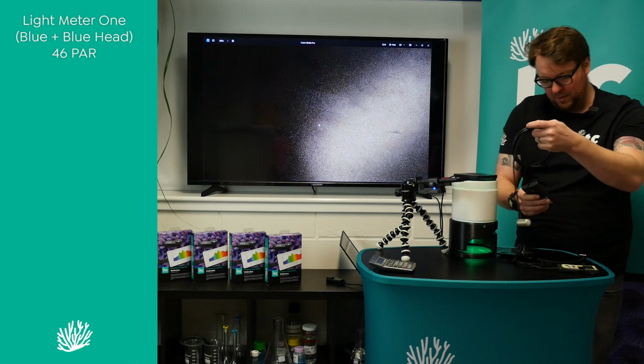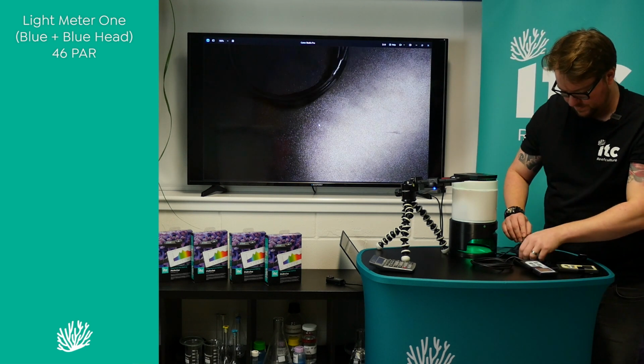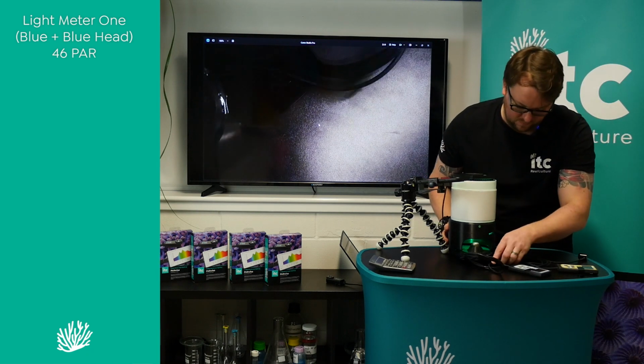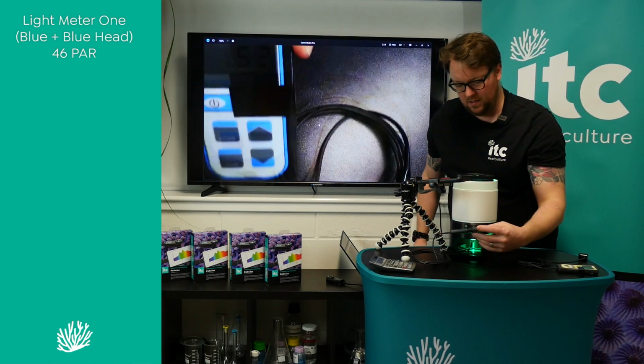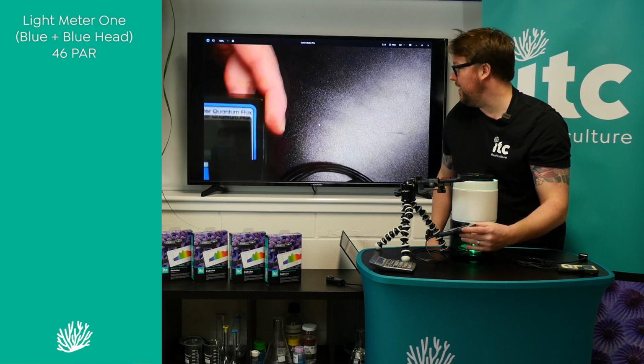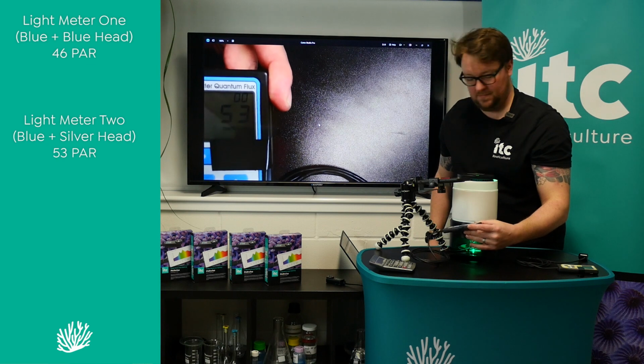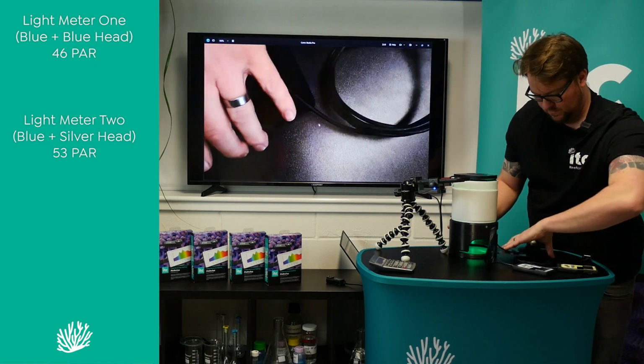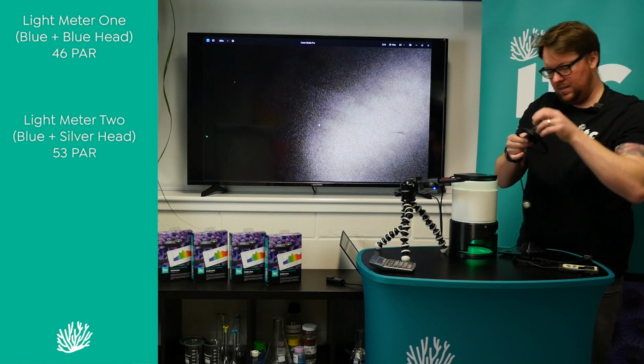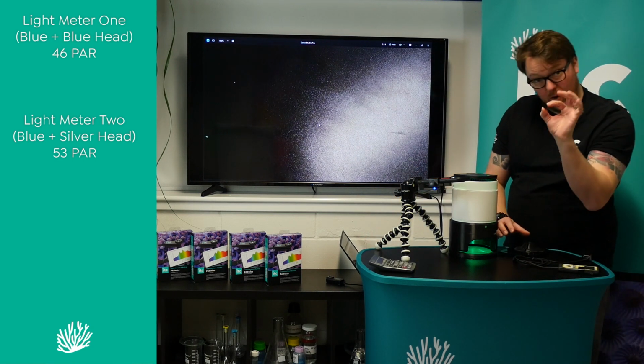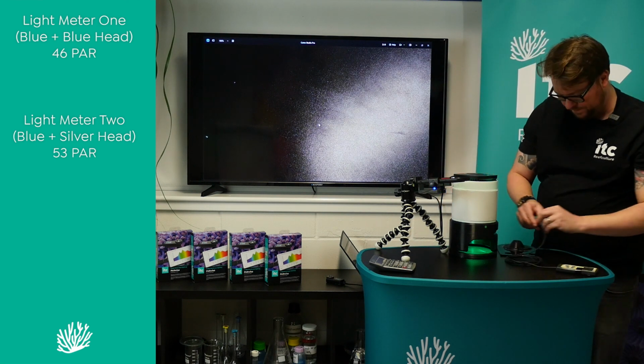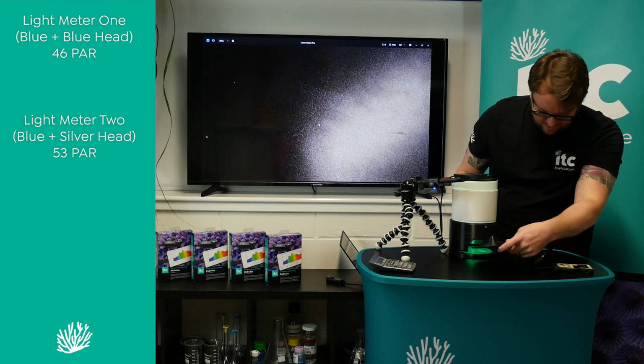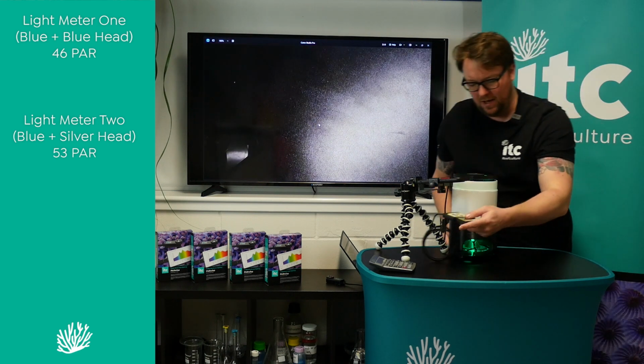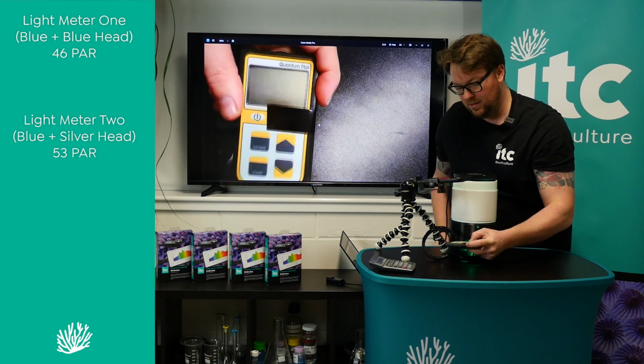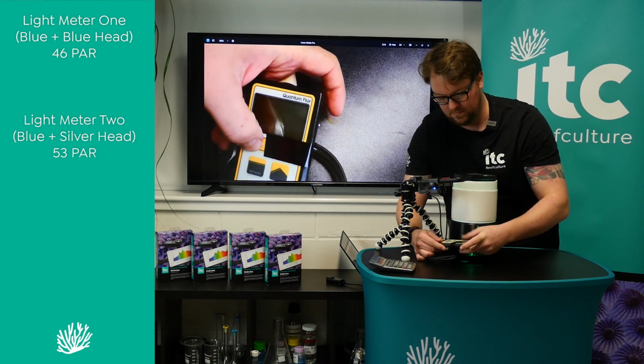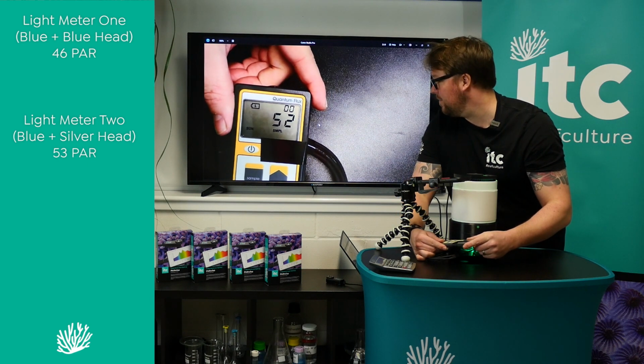Next up, we've got the other blue one with the silver head. Okay, and for this one, it's 53. Okay, so that's the two blues. And then we're going to stick in the little wedge for the yellow one. Okay, so your sensor heights are the same. Pop that in. Now this one doesn't have the immersion correction factor. And that one is on 52.